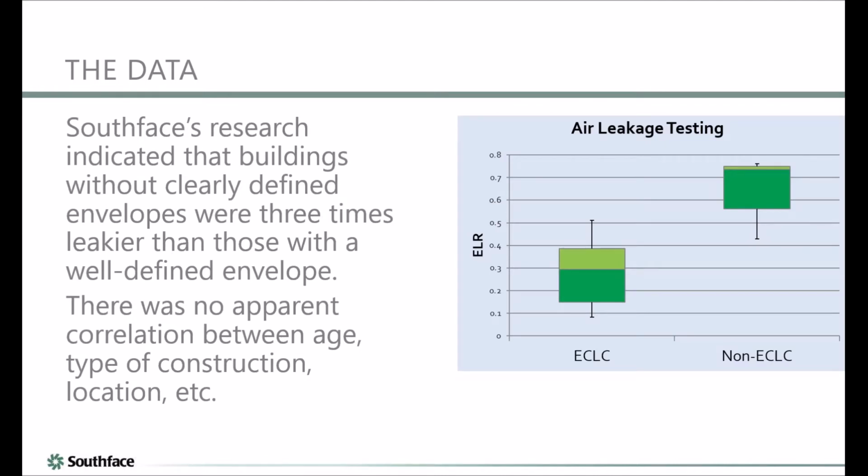Laura, this is interesting. We were involved in some research on light commercial buildings under 50,000 square feet. Initially, we looked at about a dozen smaller commercial buildings, and we blower door tested them. At the time, and probably even today, there just have not been that many commercial buildings that have been blower door tested. That number grows every year, but I would guess at the time, probably not even 1,000 commercial buildings had been blower door tested, whereas millions of houses have been tested.